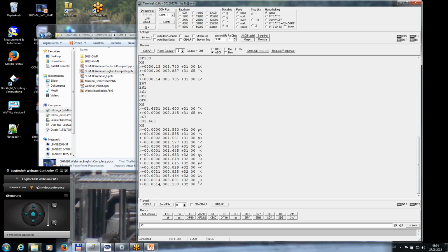This sensor, which we installed here, came back from a customer due to calibration issues. So we see there is a slight offset, but it's not as big, so it's within the tolerance. We have a 20% tolerance for these kinds of values.